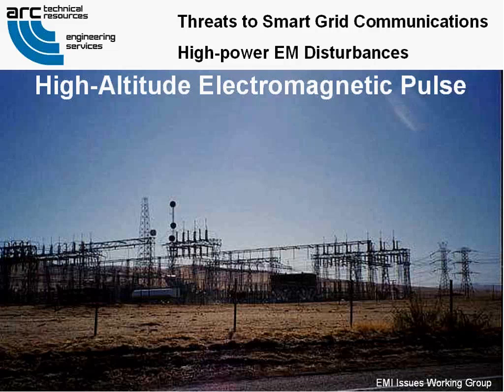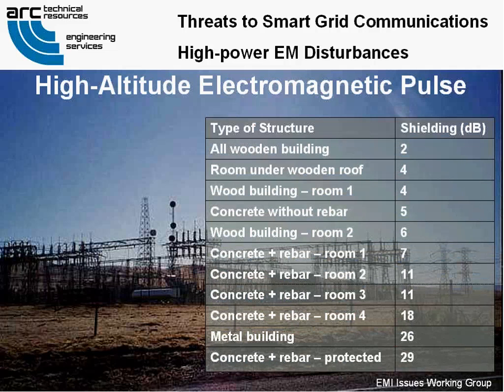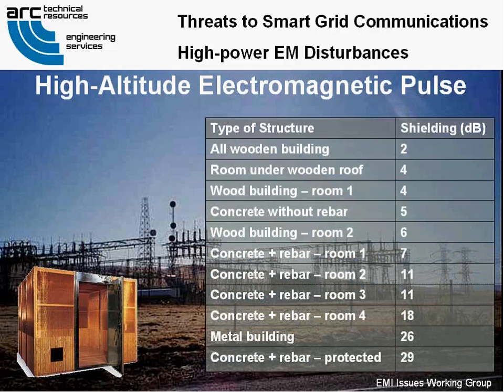In addition to damaging levels of conducted voltage into the blockhouse, the radiated E-field would penetrate the walls of most substation control houses not designed to attenuate them. As you can see from the table, typical construction methods only achieve a few dB of shielding effectiveness. Critical facilities may need to be retrofitted with architectural shielding or even a shielded enclosure with appropriate penetrations. At a minimum, critical restoration equipment can be stored in shielded cabinets or rooms for use after an event.